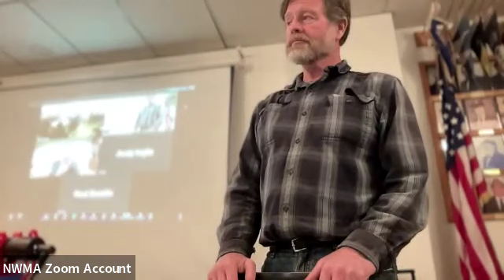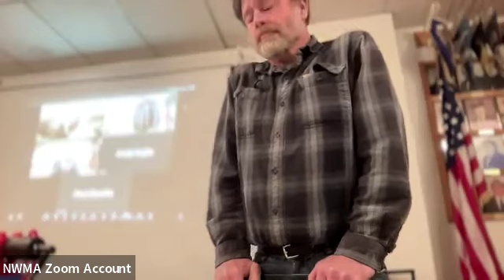But let's say you have that 100 amp windlass you were talking about, let's say 100 amp, whatever. You're going to have an amount of wire that can take that 100 amp load. And you don't necessarily need a 100 amp breaker. You could, but what you really want is a breaker that's going to stop that load on that wire from getting too much, not the load at the device.